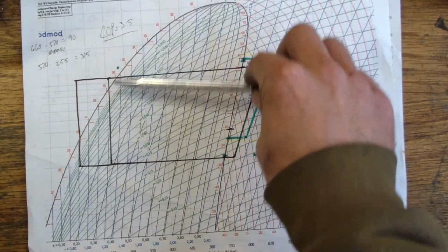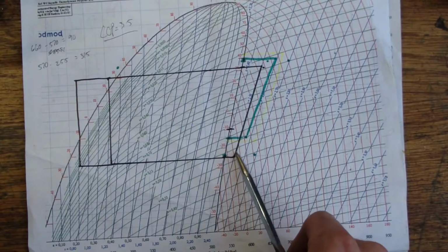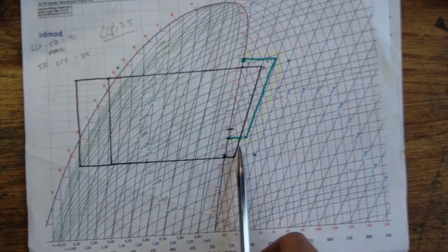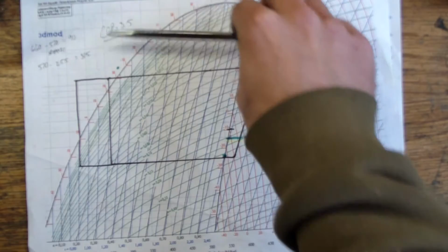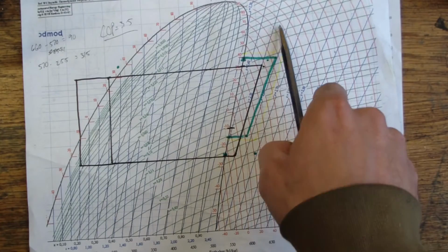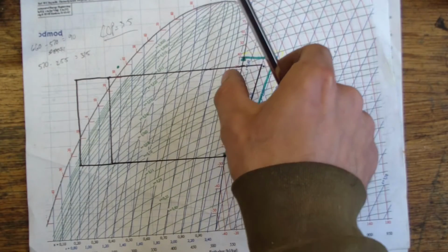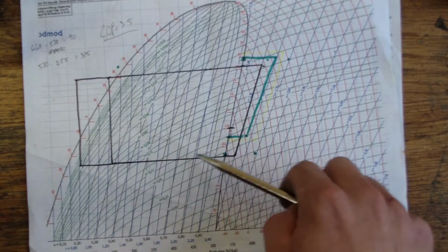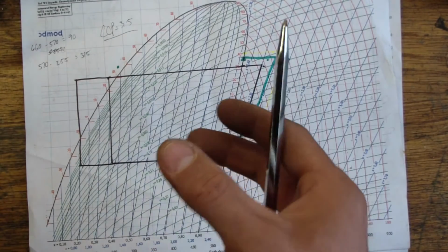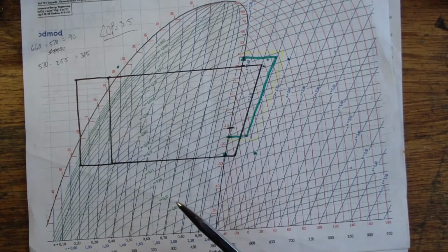So again, whenever we're looking at a larger pressure differential, assuming the compressor operates on these lines of constant entropy, whenever we have a higher head pressure, this compression line is going to come out a little bit further. So the total amount of enthalpy change during compression could be proportionally larger compared to the amount of cooling work done on your evaporator. So the theoretically possible COP decreases, and what you can actually get out of it is likewise going to probably decrease.